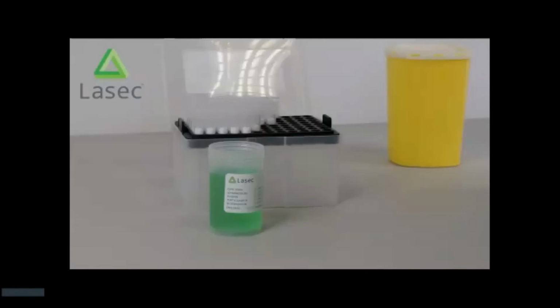Oftentimes you saw on that video the amount of corrosion that was present on that piston. That would render the pipette completely unusable. I then demonstrated how a new piston looks, and you will see that that has a very clean, very precise finish to it. That is what you are aiming for. You're making sure that the seals and O-rings are fitted, and essentially that that tip holder is clean. So do fit a filter to your large volume pipette, but the same principle can be applied to all other pipettes to make sure that they are working properly.